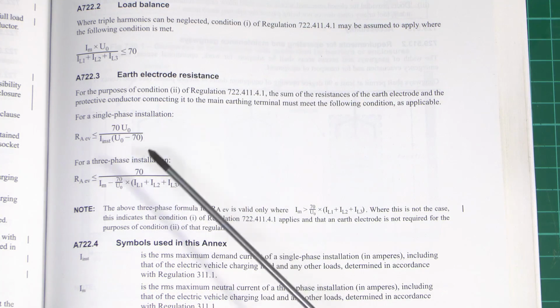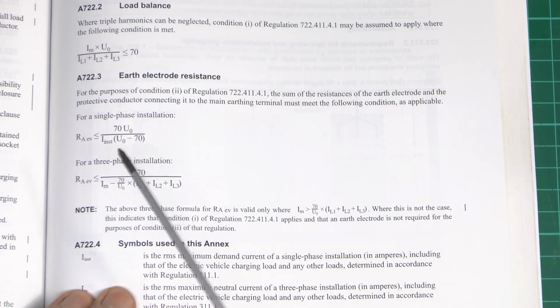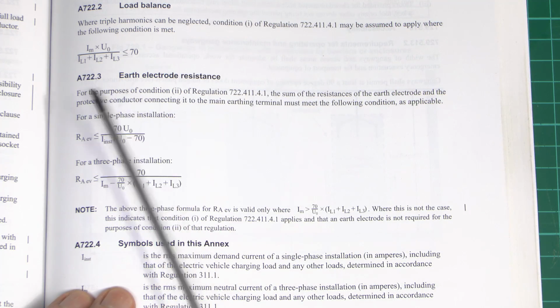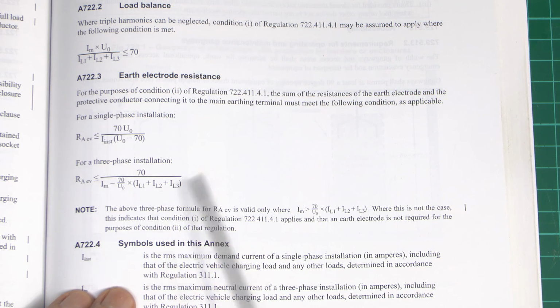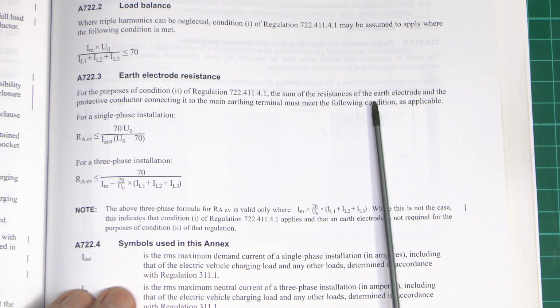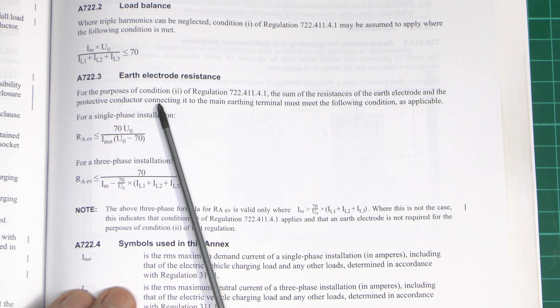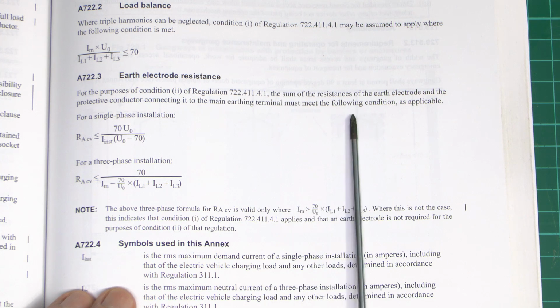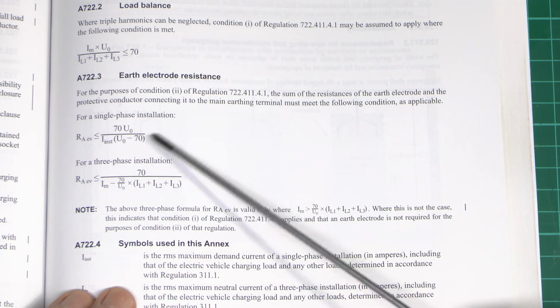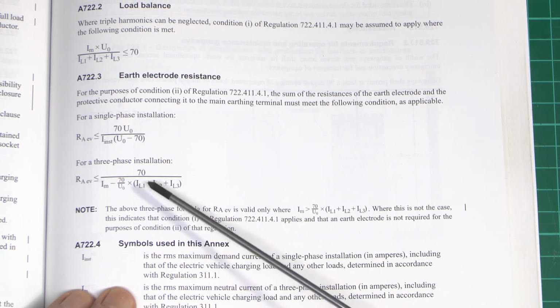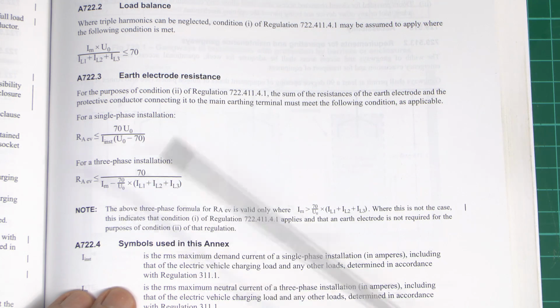Now if you were going to use that highly implausible option, this is the calculation here, and this is actually in Annex A722, that's A722.3 there, and it says here, for the purposes of condition 2 of the regulation we just looked at, the sum of the resistance of the earth electrode and the protective conductor connecting it to the main earthing terminal must meet the following condition, and we've got two here, which is basically a single phase and a three-phase installation. They both add up to pretty much the same thing. We'll look at the single phase one here.